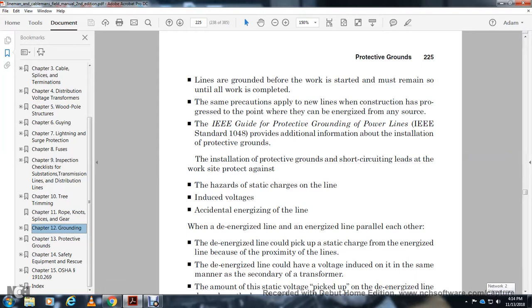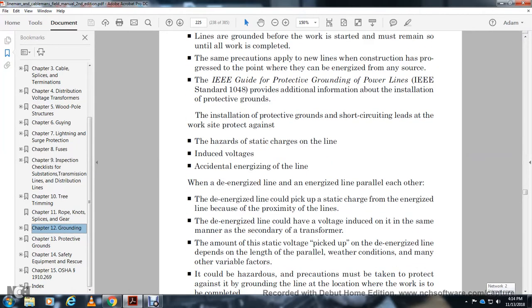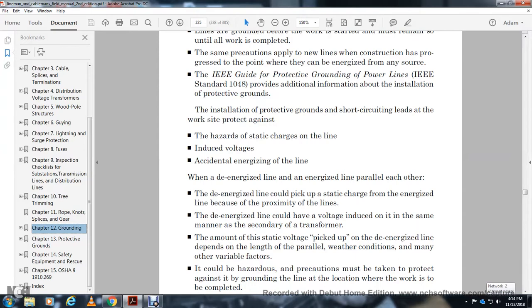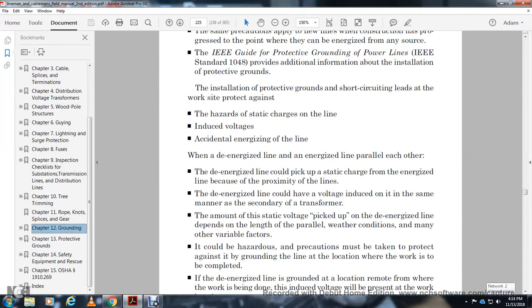The de-energized line can pick up a static charge from the energized line because of the proximity of the lines. The de-energized line can also have voltage induced on it in the same manner as a secondary transformer. The amount of static voltage picked up by the de-energized line depends on the length of the parallel, weather conditions, and many other variable factors. It could be a hazard.